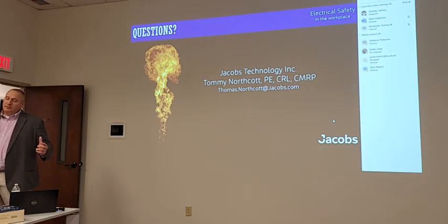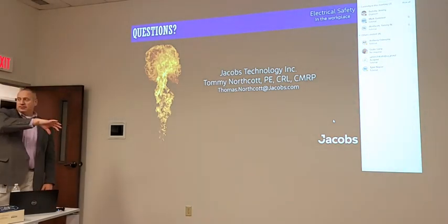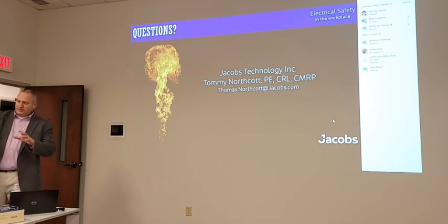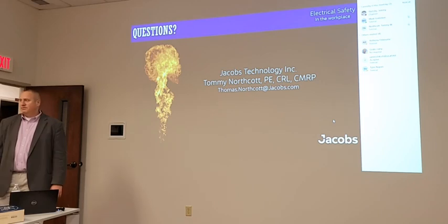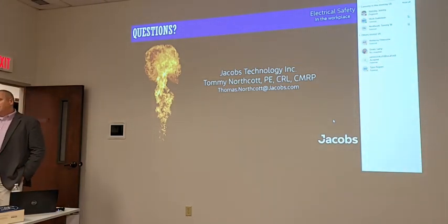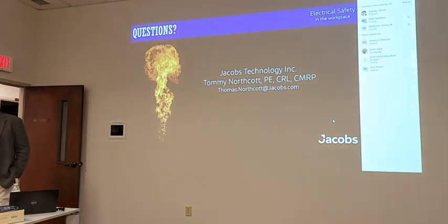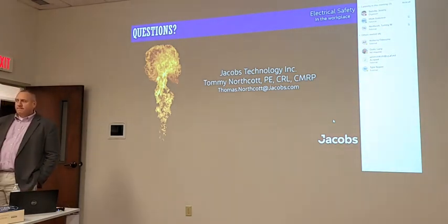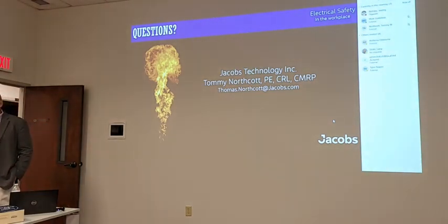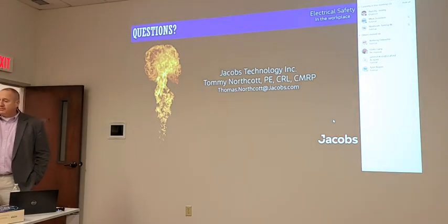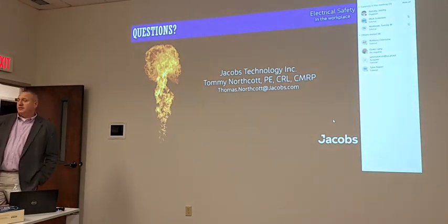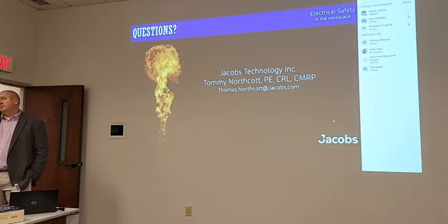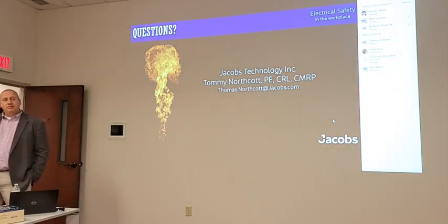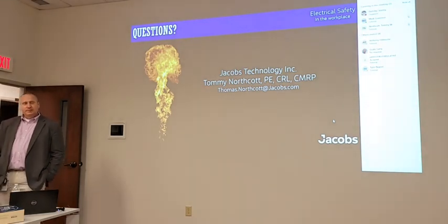Right. And then turn around and provide that analysis back to the host, which then plays into the rest of this. Right. So it's not so much that this is going to change more, but there may be some differences they have to account for, particularly if there's a lot of motors. Right, motor contribution. But would it change the model as much as it would change the available short circuit current that feeds it? It wouldn't change the available short circuit current. It would potentially change some of the incident energy levels in other places of their system. So they would have to update their system. Okay. It could affect another, unrelated panel, right? Because that motor energy could traverse over to another panel. Right, yeah.